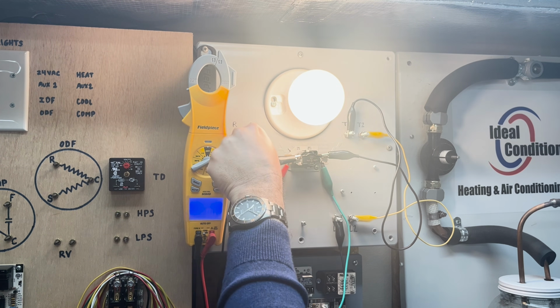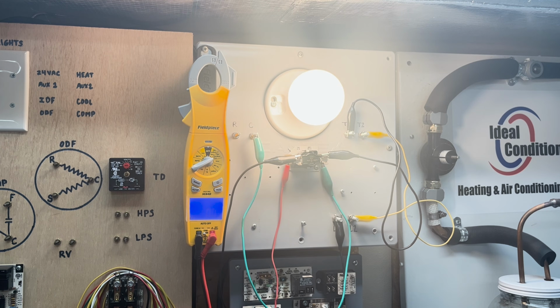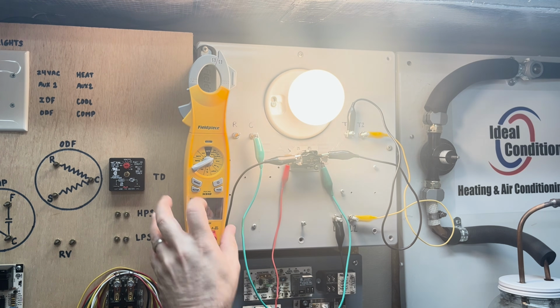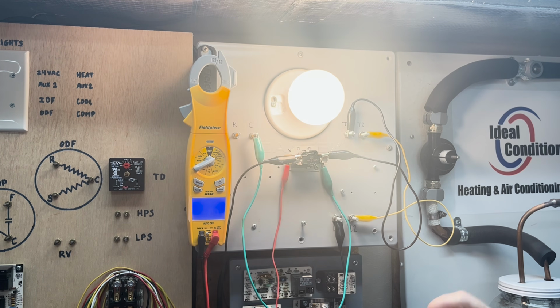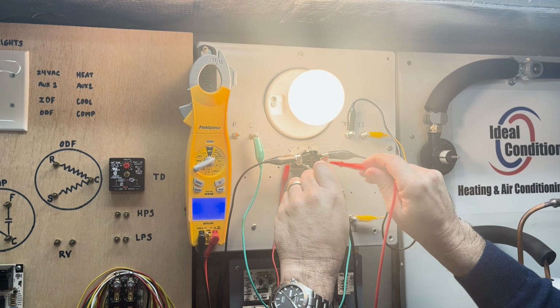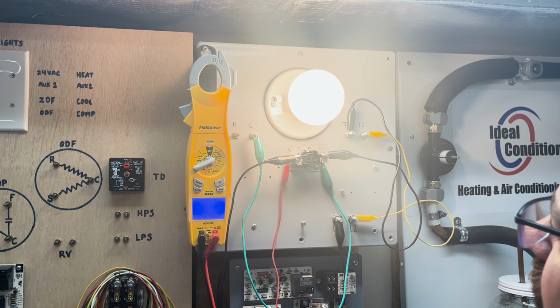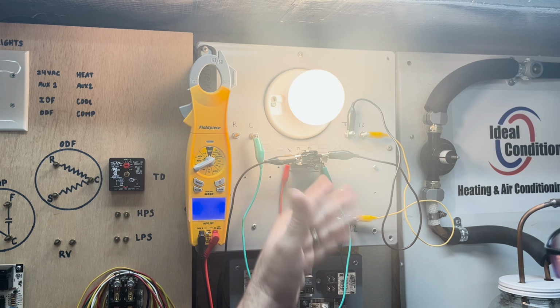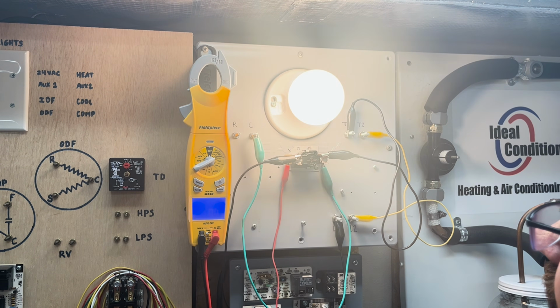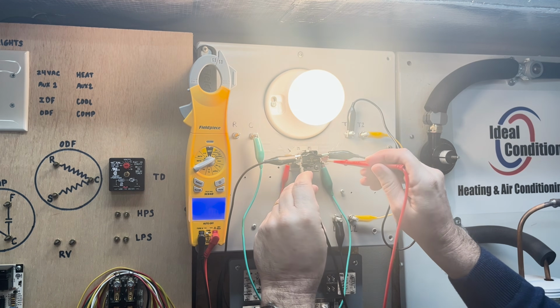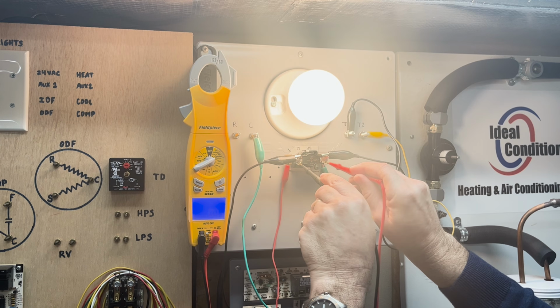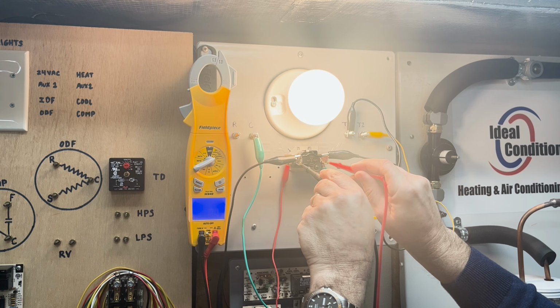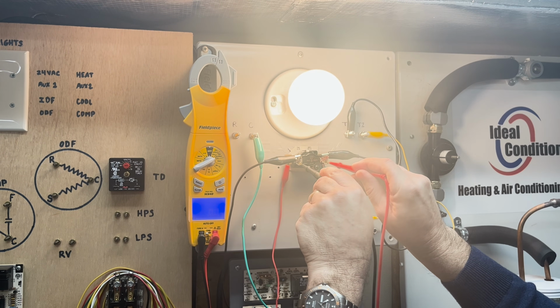But if we were to remove power, and let's just say the relay's stuck in a closed position and the load won't shut off. You go to your relay. Hey, I'm reading 0 volts across it. Yeah, that's why my load's running. And as we know, 45 seconds of this, it'll shut off. And then I'll show you how we have L1 and L2 across there. And I'll explain why we have L1 plus L2. How do we go from 0 volts? I'm going to leave it there. How do we go from 0 volts to 242 volts? How does that happen? Come on, relay.